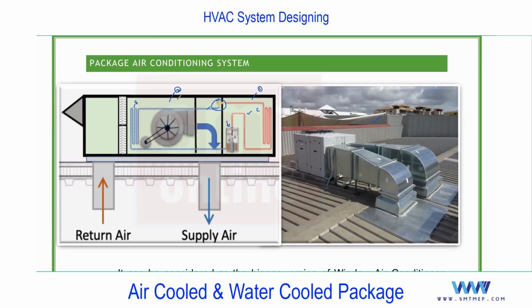And remember this section 2 is with double skin, and the term double skin you'll find in the specification. Double skin refers to a body with insulation, meaning here you'll find the insulation. And why is insulation required? Because you'll find the cooling effect on the evaporator coil. On this side, we don't require insulation because we are interested to reject the heat. You'll find the fan on the top, so the air will be sucked from outside and through. So we are interested to reject the heat. But on this side insulation is required to avoid the loss of energy, meaning loss of cooling.